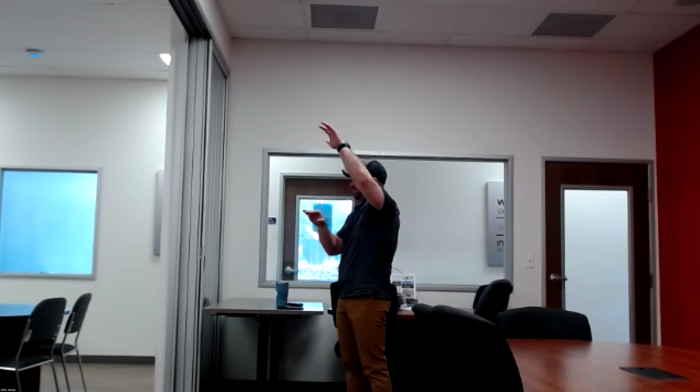The other thing that I see a lot is CO detectors not placed correctly. CO detectors need to be within 15 feet of each bedroom door and on each floor. That can include split level homes. If you've got a home that's technically three levels, there will need to be three CO detectors installed there and that kind of stuff.